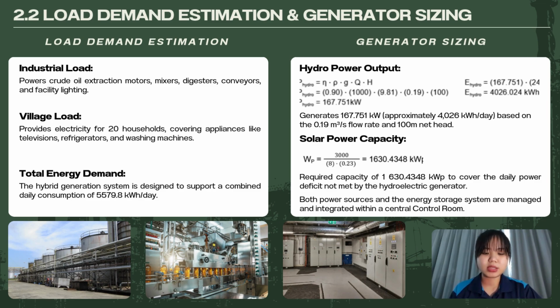For the generator sizing, the hydropower output it needs to generate is 167.751 kilowatt, which is approximately 4,026 kilowatt-hour per day, based on the 0.19 m³/s flow rate and 100 meter net head. For the solar power, the required capacity is 1,630.4348 kilowatt to cover the daily power deficit that is not met by the hydroelectric generator. Both power sources and the energy storage system are managed and integrated within a central control room.